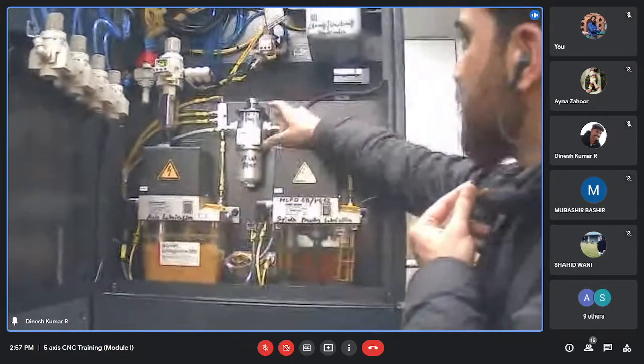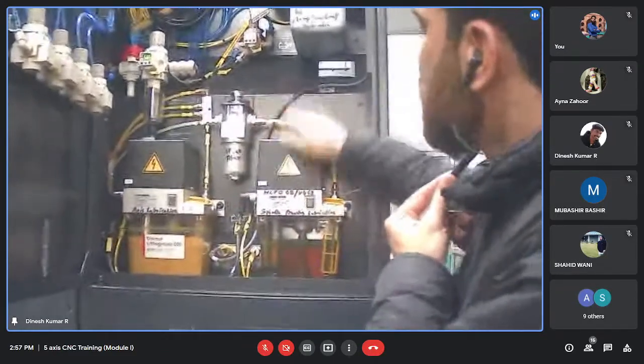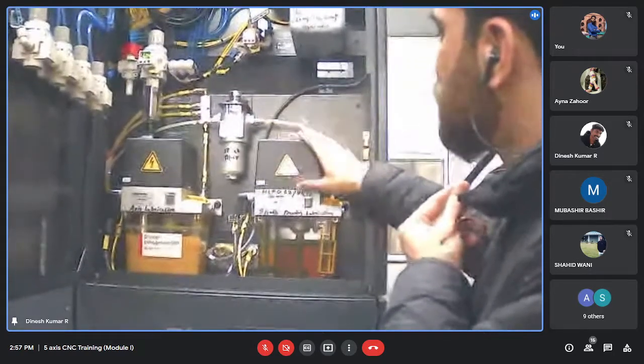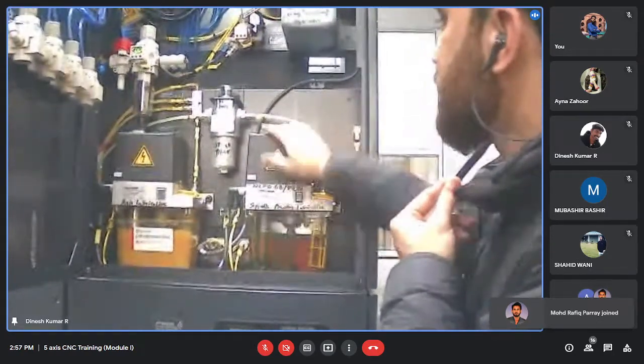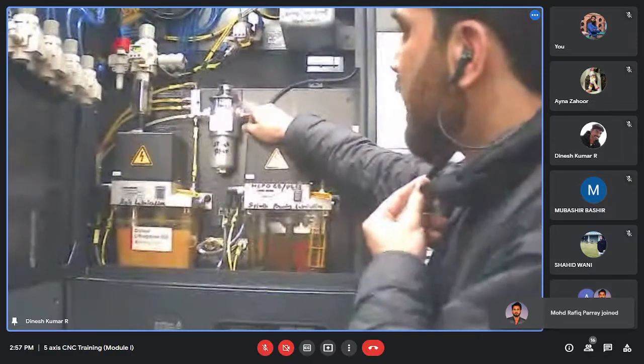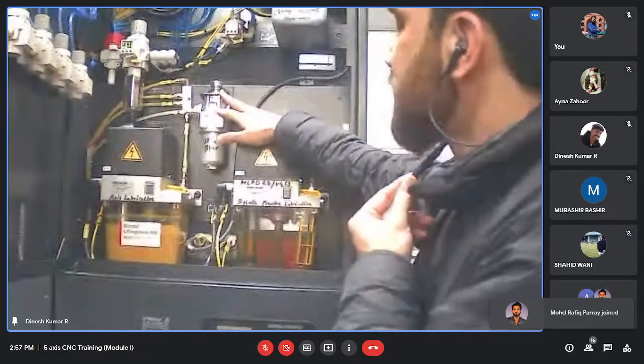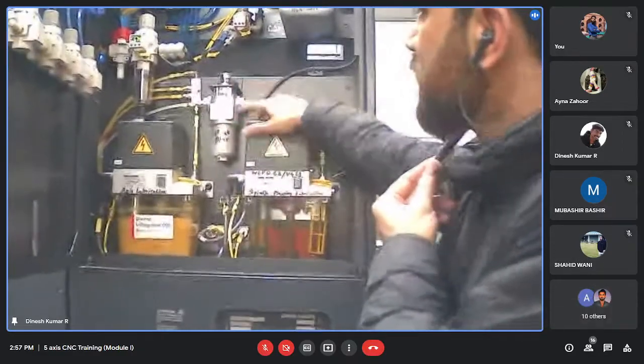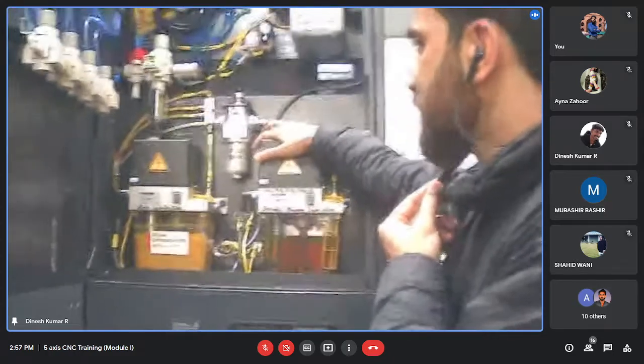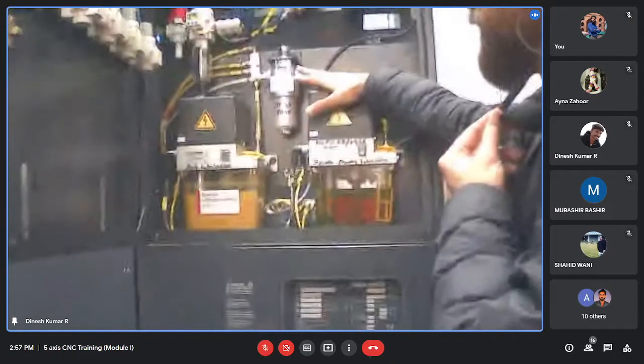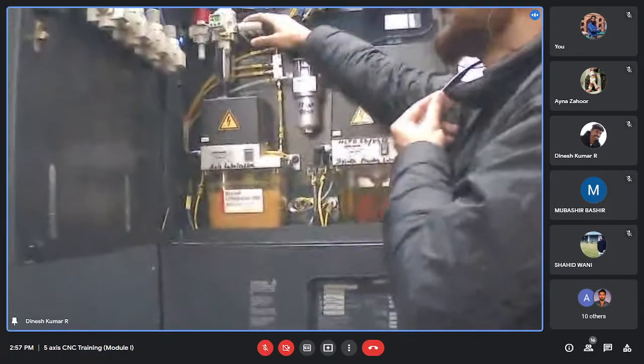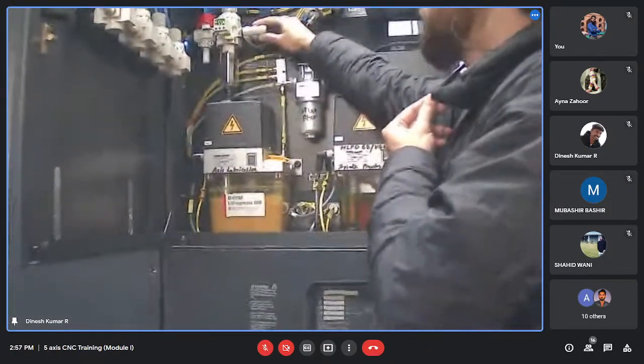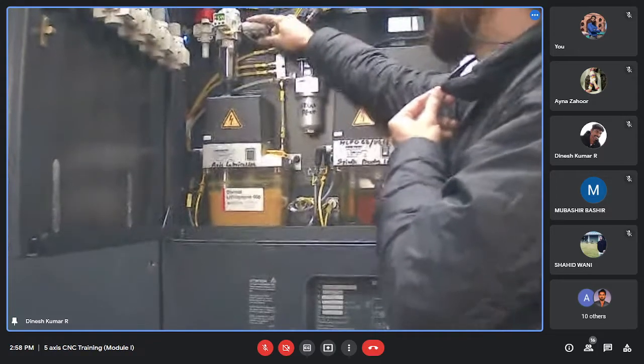We also have this filter unit - the oil supplied to the bearings from this tank is first filtered here, then it's mixed with some air, making it an air-oil lubrication mixture provided to the bearing. Also, the compressed air supplied to the machine is filtered from this unit.